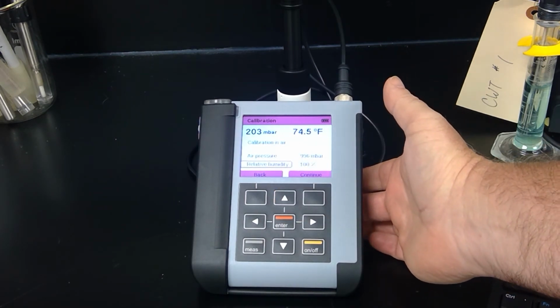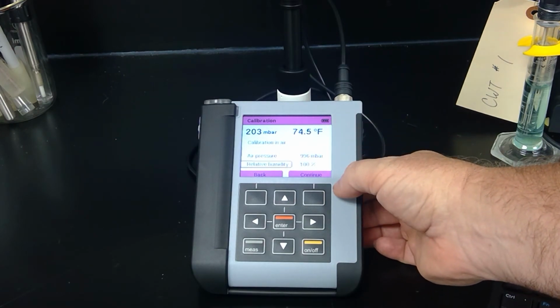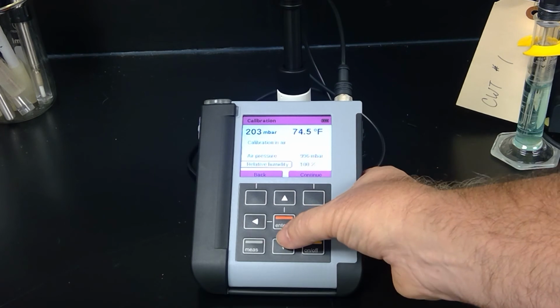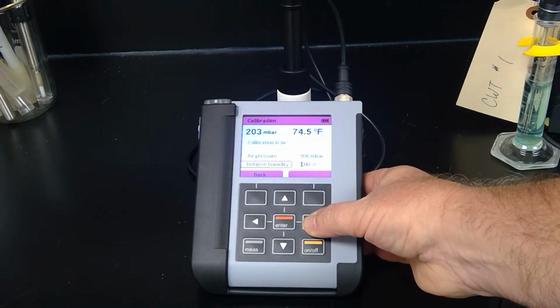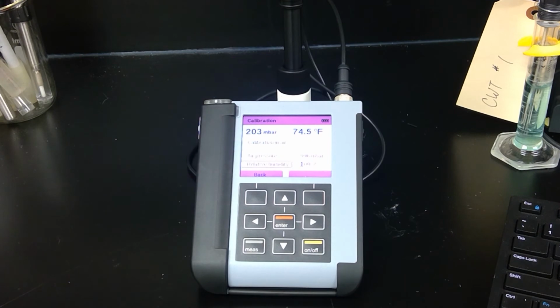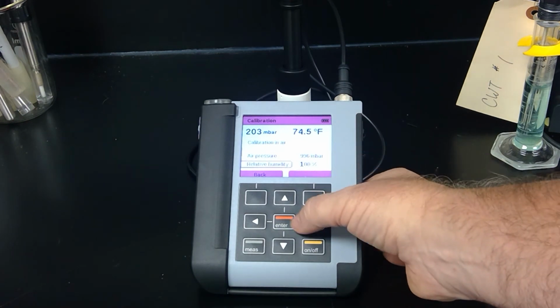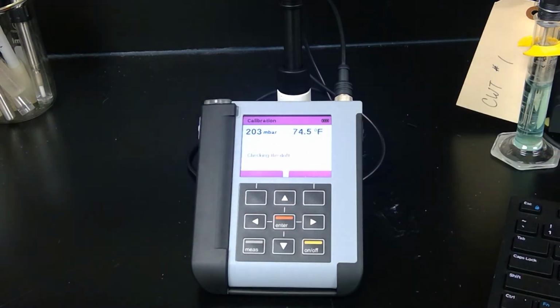Because, as you may be aware from previous videos, the Portavo has an integrated pressure device, so it already knows what your air pressure is. And because we have put this into the calibration cap, and we've left it in there, let's say 30 minutes, we know we are at 100% humidity. So I hit continue. In this part of the video it will take about 30 to 60 seconds to complete the calibration. Once the calibration is complete, we're able to take it directly into the field for grab samples and checking loops, things of that nature.